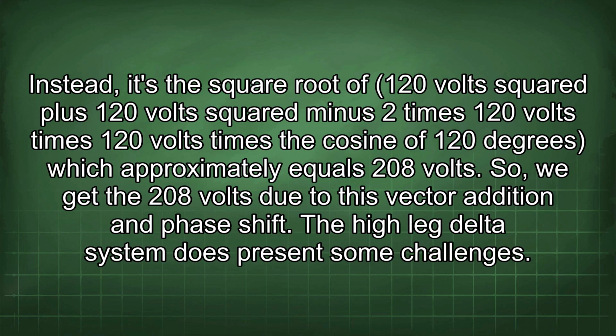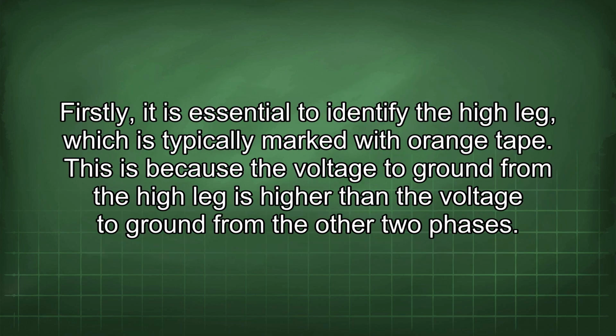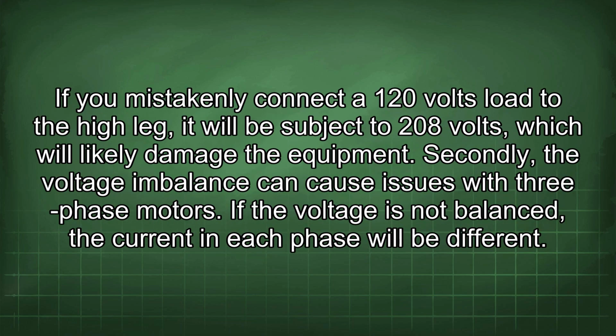The high leg delta system does present some challenges. Firstly, it is essential to identify the high leg, which is typically marked with orange tape. This is because the voltage to ground from the high leg is higher than the voltage to ground from the other two phases. If you mistakenly connect a 120 volts load to the high leg, it will be subject to 208 volts, which will likely damage the equipment.